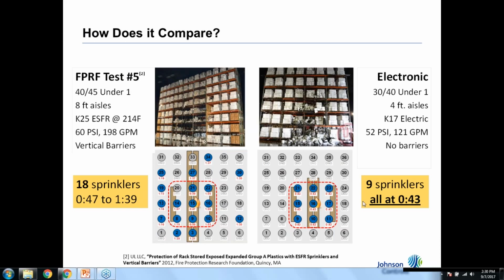We did a test of 40 foot of exposed expanded plastic under a 45-foot ceiling, utilizing 8-foot aisles, K25 ESFR sprinklers at 214 degrees. In this case, there were vertical barriers, which is what's required now when you deal with exposed expanded plastics. And as you can see, that was the phenomenon I was talking about: if you look at the lower left, sprinkler number 3, which is not in the fire area itself, never actuated. Yet sprinklers number 30 and 34 way off to the right, and sprinkler number 12 at 1 minute and 35 seconds, actually actuated outside of the fire area.